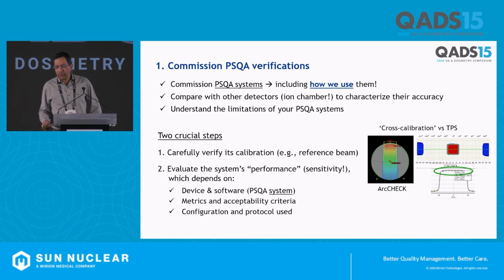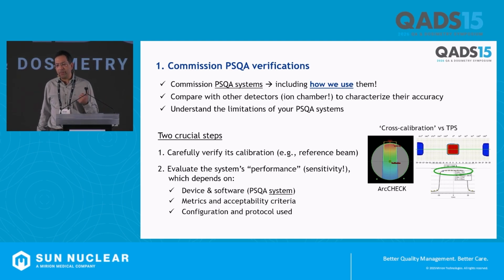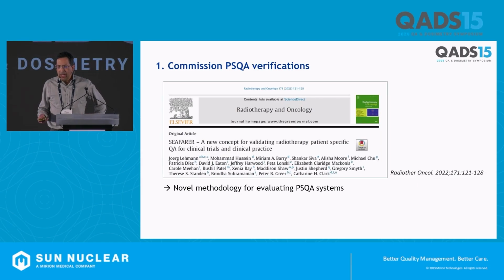And second, you need to evaluate the system's performance, mainly its sensitivity, meaning its capability to detect errors. And this depends on the device, on the software, because it's not only a device, that's why I call it a system, but also it depends on the metrics, on the acceptability criteria, the configuration, and the protocol you used, so on how you use the system. And I strongly recommend this paper that proposes a novel methodology for evaluating PSQA systems, mainly by introducing forced errors, quantifying the dose impact, and then evaluating if the PSQA system is able to identify those errors or not.